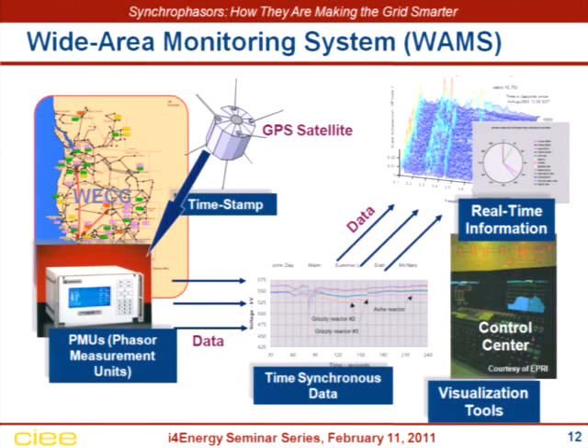These phasor measurement units, as they're called, are being employed in more and more substations to provide this synchrophasor measuring point. The analog data from the current transformers and voltage transformers is taken into this GPS, into what's called the phasor measurement unit. From now on, every time I say phasor, just think synchrophasor, because that's what I mean.